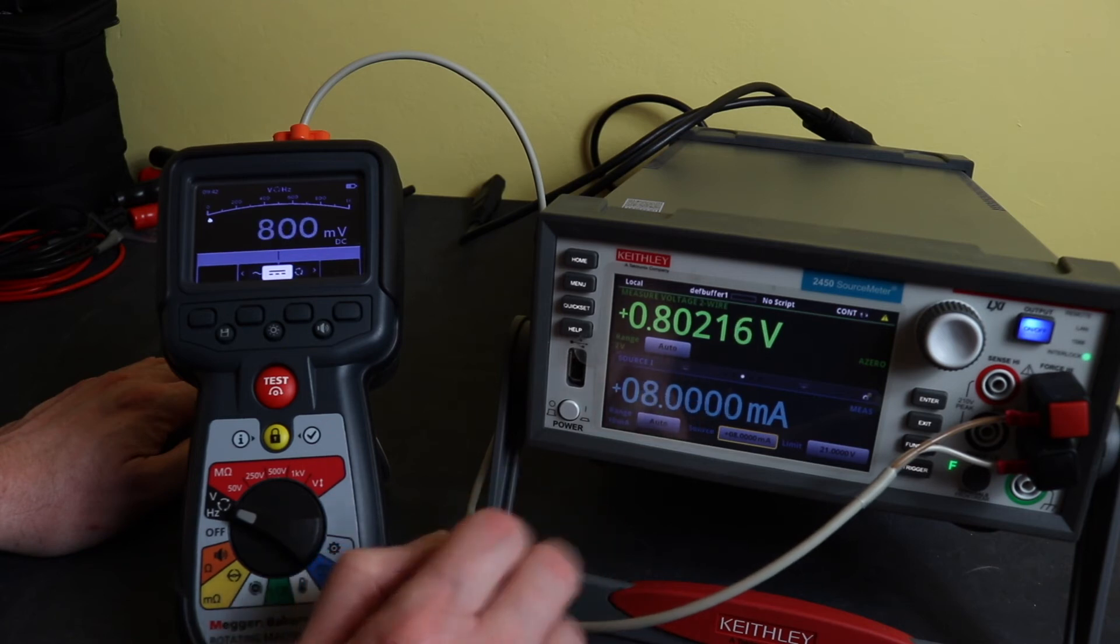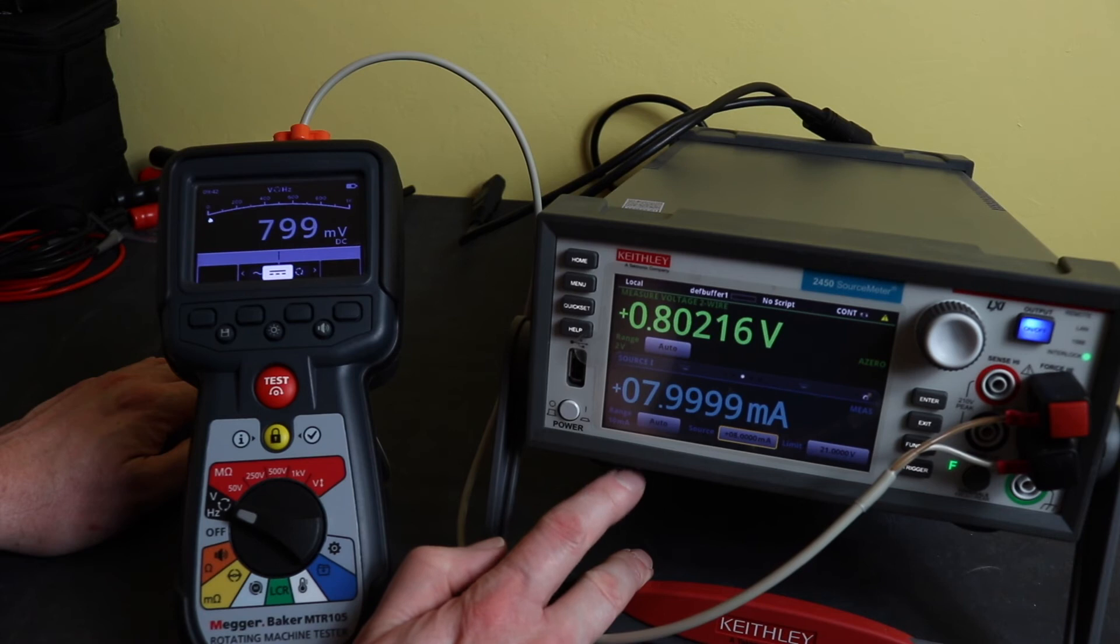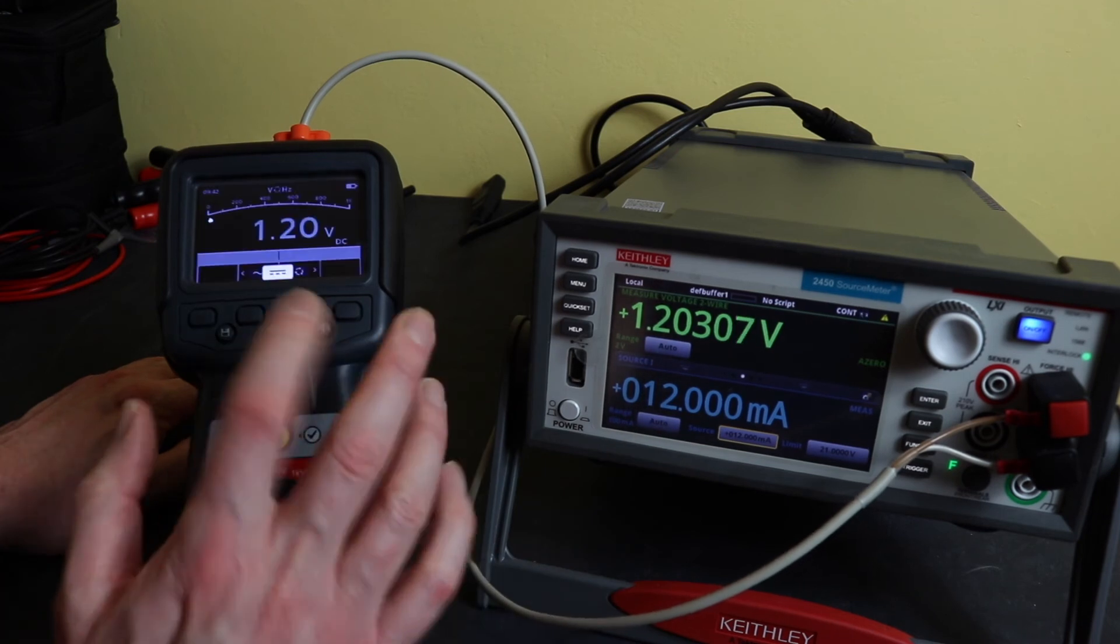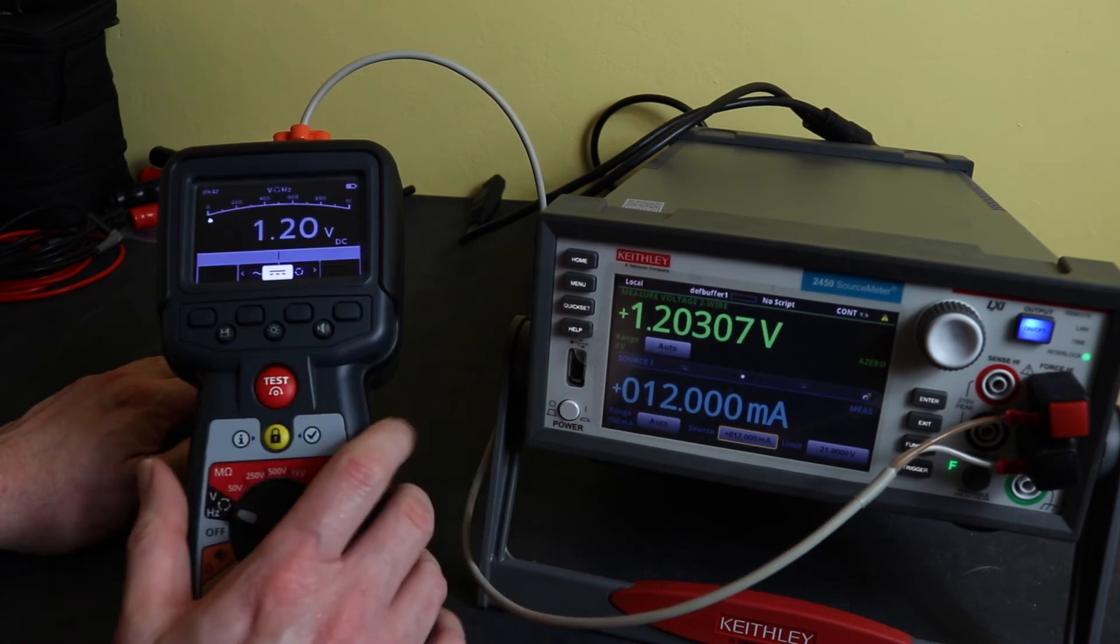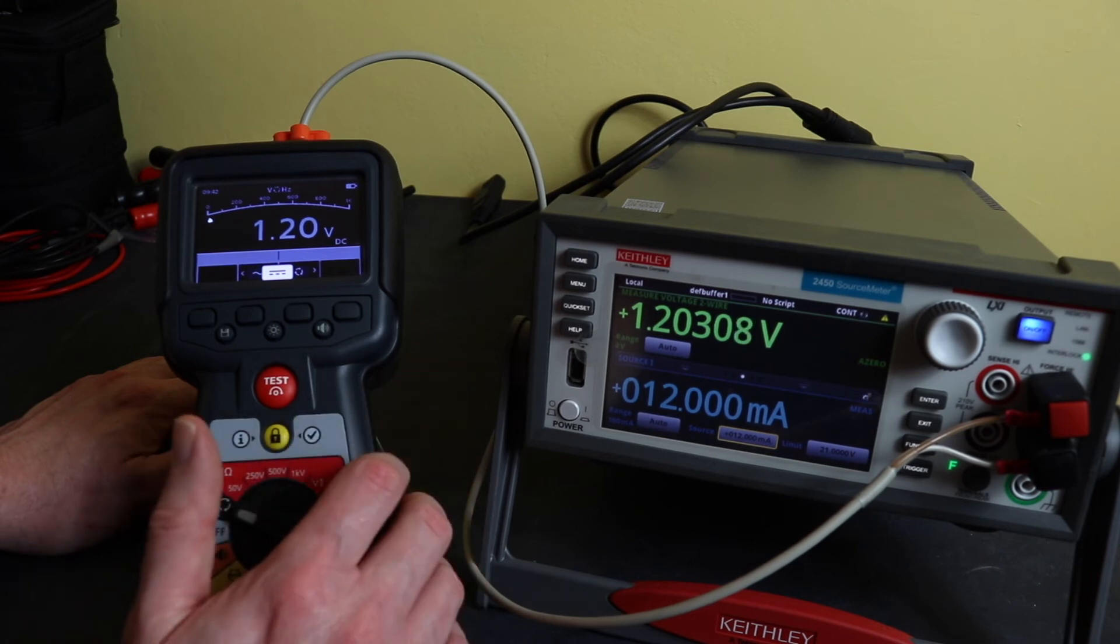So on eight milliamps, 7.99. Yeah a little bit of flickering, I'm not sure why this instrument's flickering really it shouldn't be. Okay try 12 milliamps.